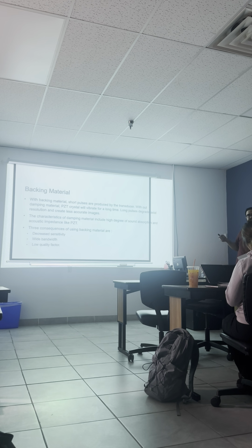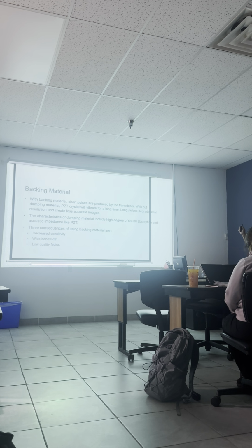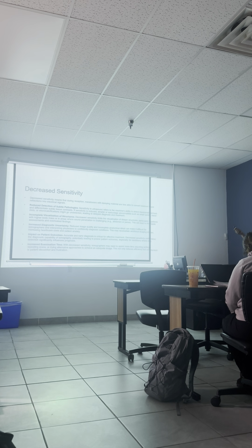It stops the vibration. Yes? Okay. It has 3 main consequences. Those are decreased sensitivity, wide bandwidth, and low quality factor, or low Q factor. Okay? We're good with this? Okay, so decreased sensitivity.